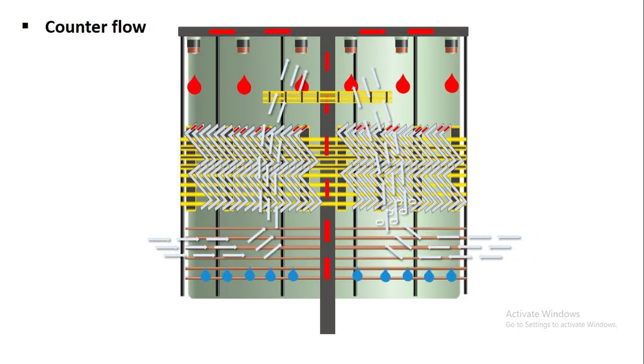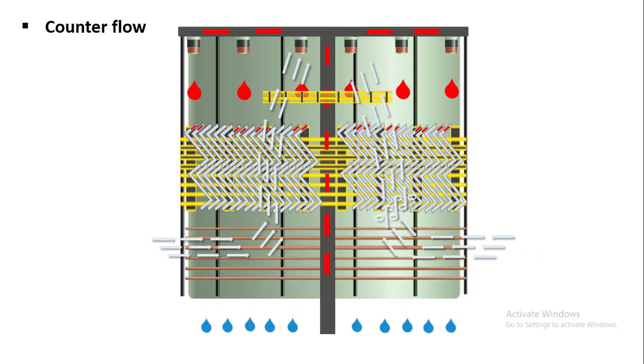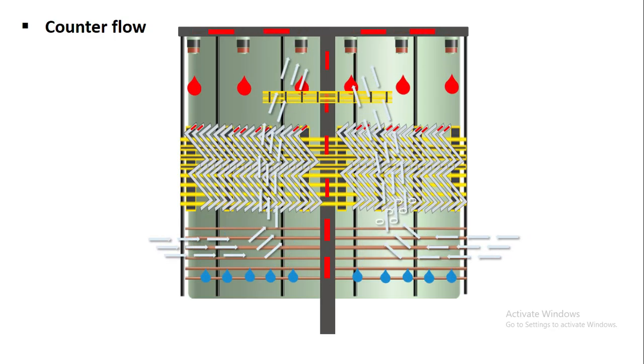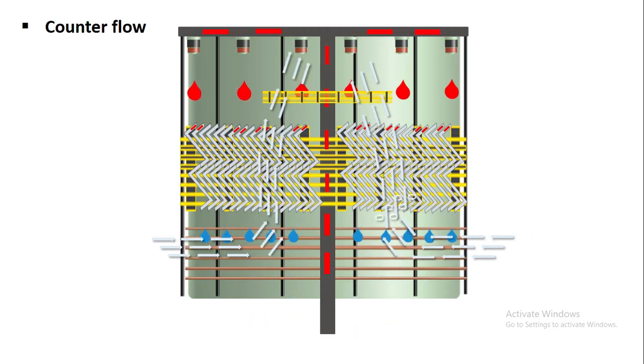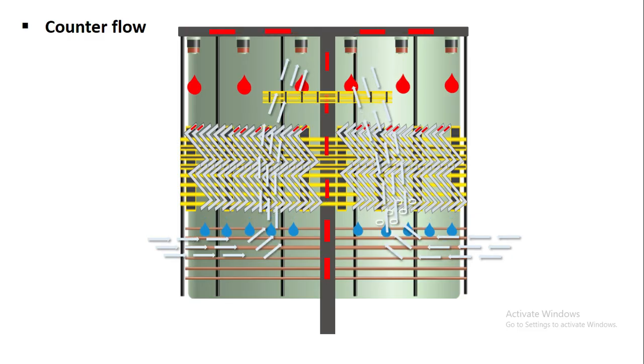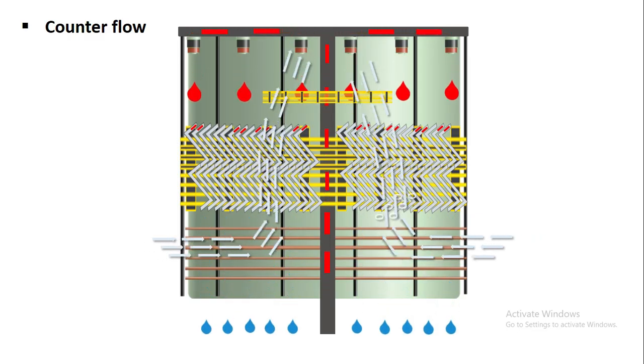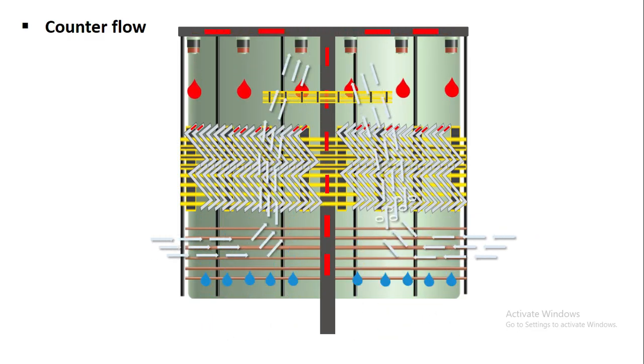In the counter flow cooling towers air flows upward through the fills while water flows downward from the top. As you can see in the working animation air and water move in the opposite direction. The main advantage of counter flow cooling tower is its compact design. The more compact design effect in better thermal performance of this counter flow cooling tower.